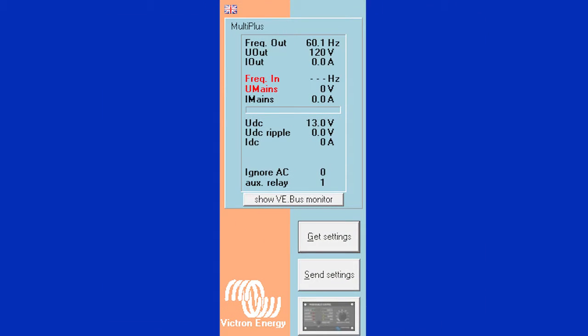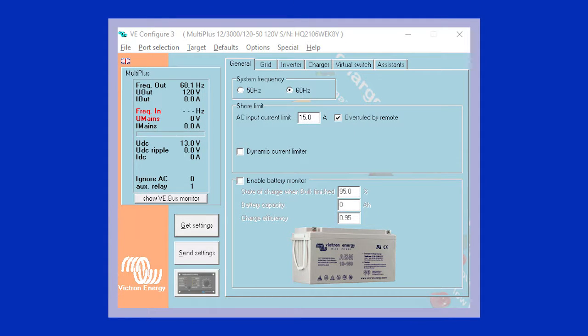So on the left side over here, this actually gives you information about what's going on with the inverter, how much power is coming in or out. But we're gonna look over here in each of these little tabs. We'll go through and check any changes that we might need to do. So first of all, the general settings, system frequency is 60 Hertz. AC input current limit, 30 amps would be a good setting for this. It actually can go up to 50 amps.